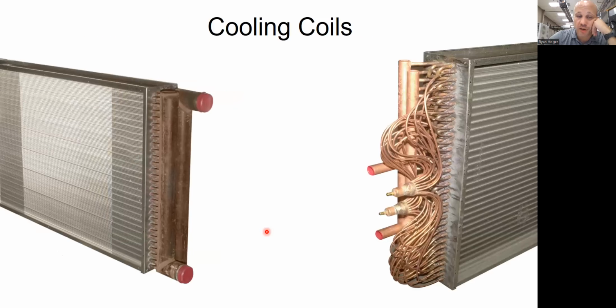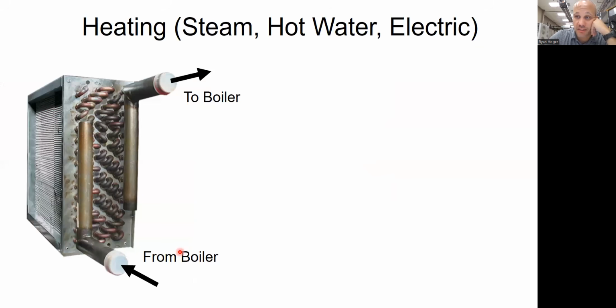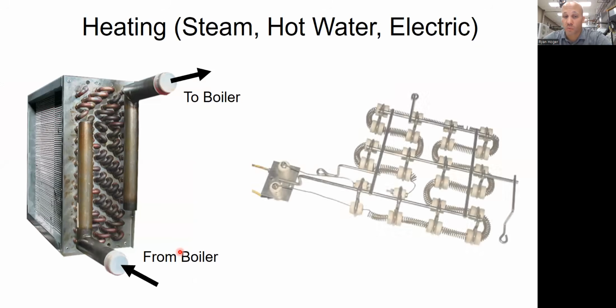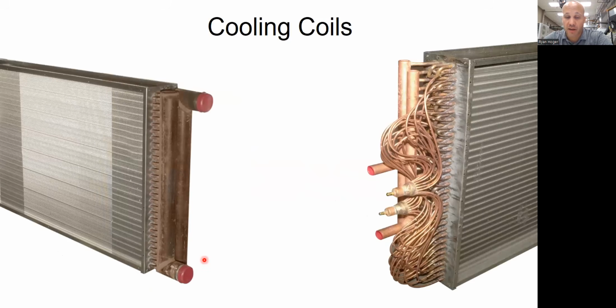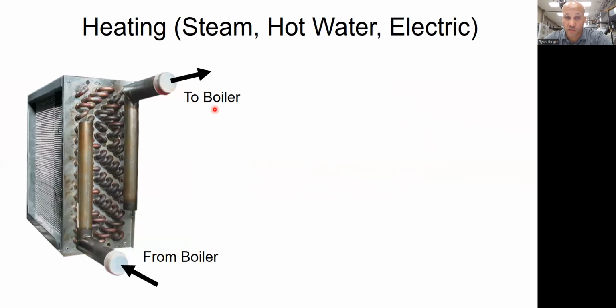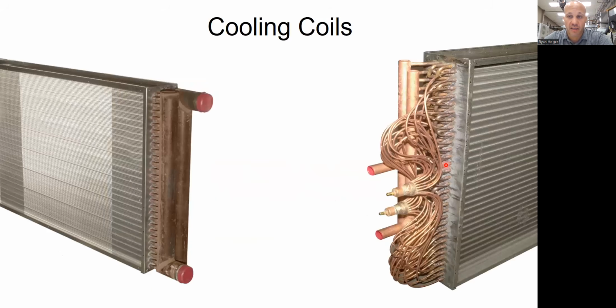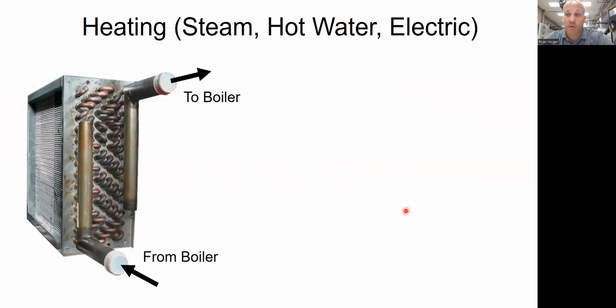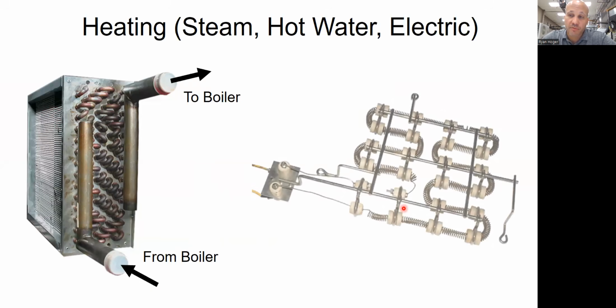Be careful, because when you open up this and you see this, it might not be a cooling coil. It might be the hot water or steam coil, because they look the same, right? The cooling coil will have a condensate catch drain pan on the bottom over here. The heating coil won't. So you might have this for heating, and then just upstream of that, you may have this for cooling. So you've got to make sure you're on the cooling coil, because the heating hot water coil looks exactly like a chilled water coil. So once I know my type of cooling system, my next question is, what kind of heating system do I have? Because that's going to make a difference on what I can offer as well.